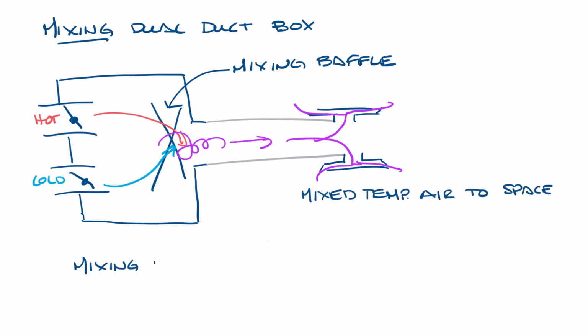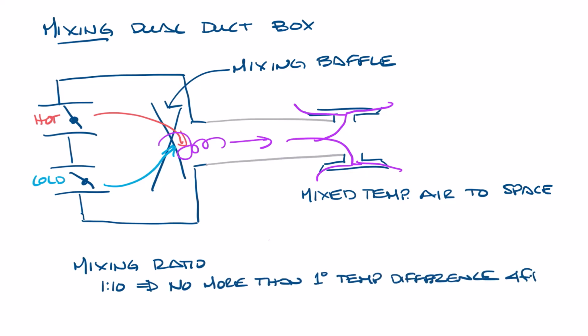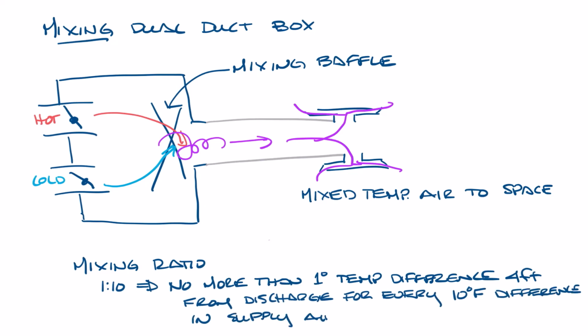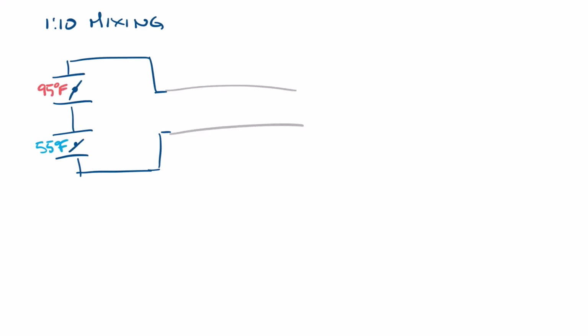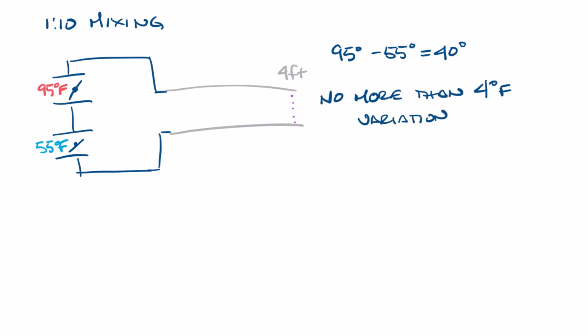We describe how well a dual duct box mixes as its mixing ratio. A 1:10 mixing box, the typical mixing ratio, has no more than 1 degree of temperature differential 4 feet off the discharge for every 10 degrees of supply air difference. So let's move this over one more time and look at this with some numbers. So for 1:10 mixing, let's say your cold air is 55 degrees and your hot air is 95 degrees. And let's add 4 feet of ductwork. So 95 minus 55 is 40 degrees. So if I were to take a traverse of temperatures at 4 feet from the discharge, you would have no more than 4 degrees variation in a 1:10 mixing box.